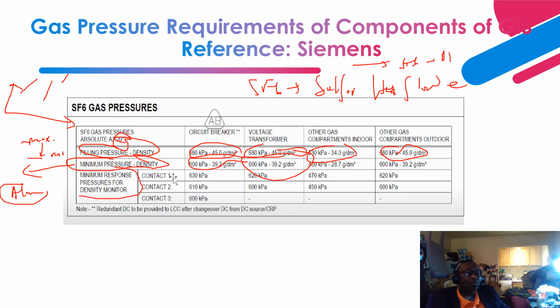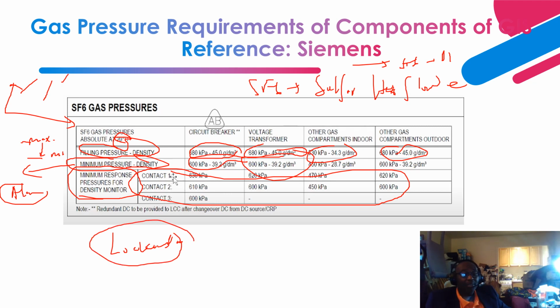Next is your minimum response. This is when your circuit breaker contacts basically lock out. It means that the pressure has fallen to a level at which it is not going to operate. When it falls to that level, if it is truly a legitimate leakage alarm, then you have to tie in the OEM, investigate and implement the required corrective action.